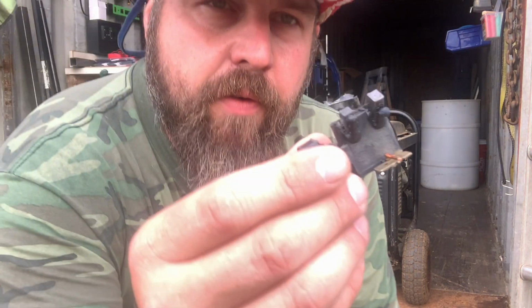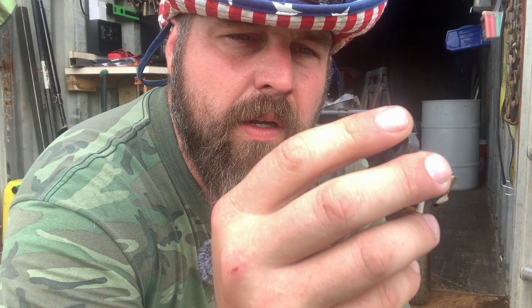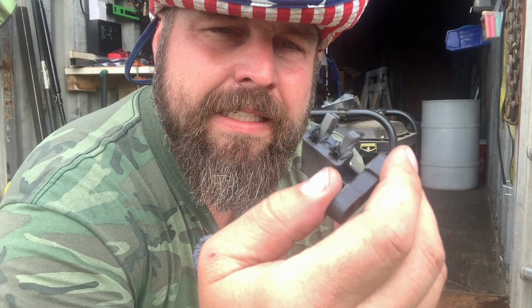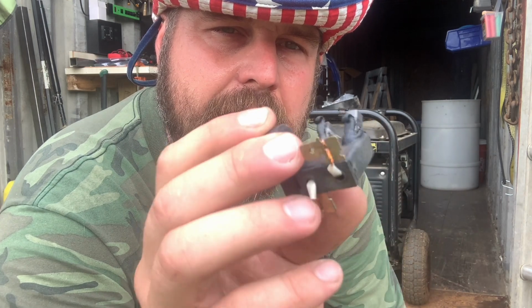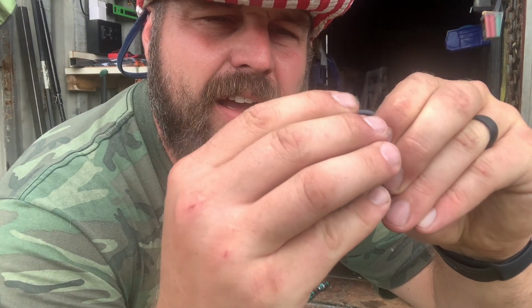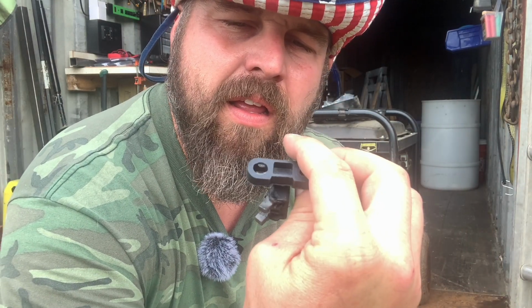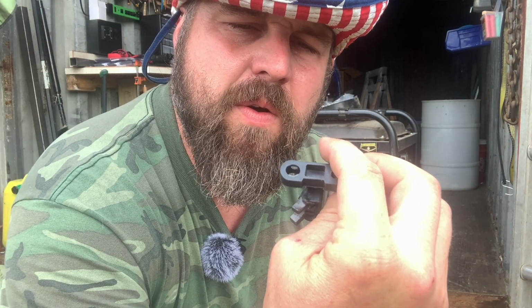It might not be the voltage regulator. These are the brushes, guys. So, yeah. These got hot. And these, oh, that's what happened. Smoked. I'm just gonna replace the brushes and put that other voltage regulator back in. We're gonna crank. Let's see if we get power.